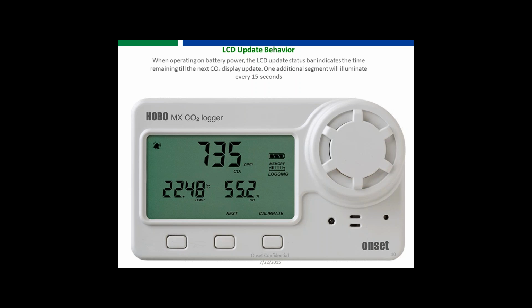So what we've done, and again, this kind of highlights what happens: the LCD status bar will indicate the time remaining until the next CO2 display update. Basically, you have 20 segments, and each one illuminates after 15 seconds. So if you multiply 20 times 15, you'll get 300 seconds, or 5 minutes. So when all 20 segments are illuminated, the refresh of that CO2 measurement happens.